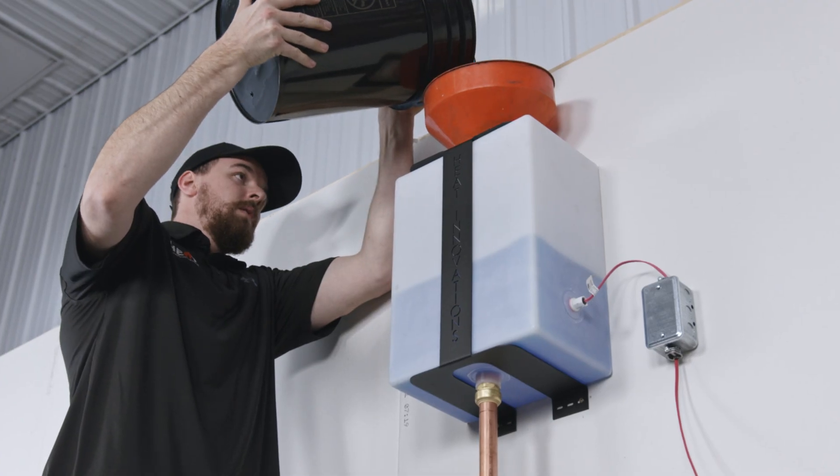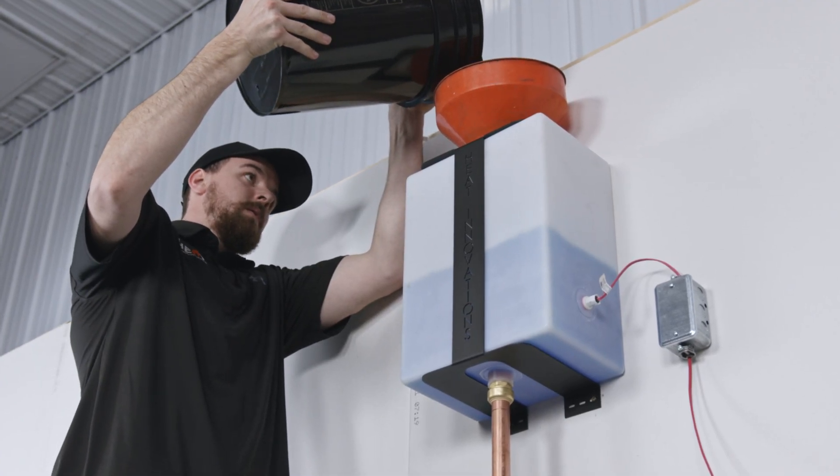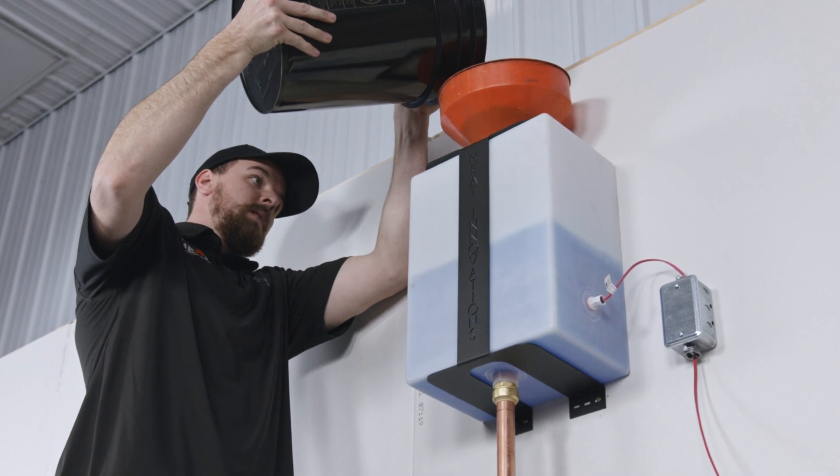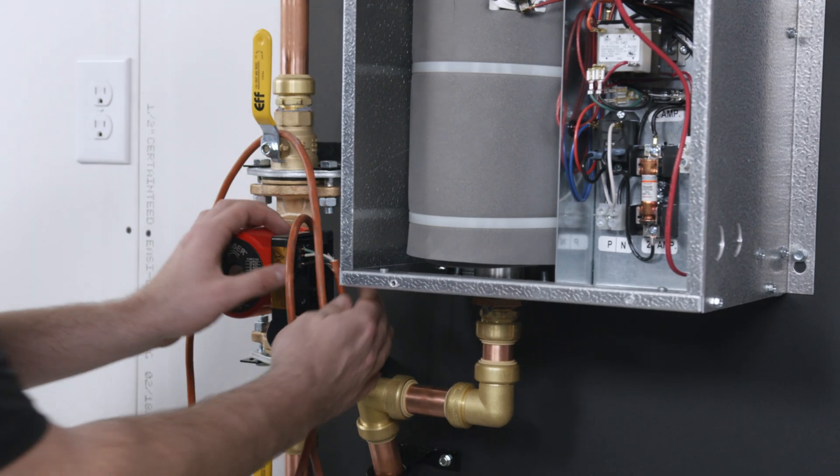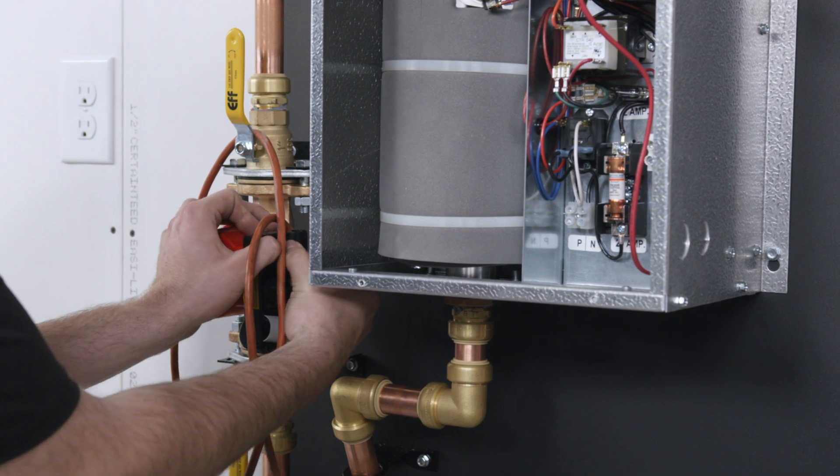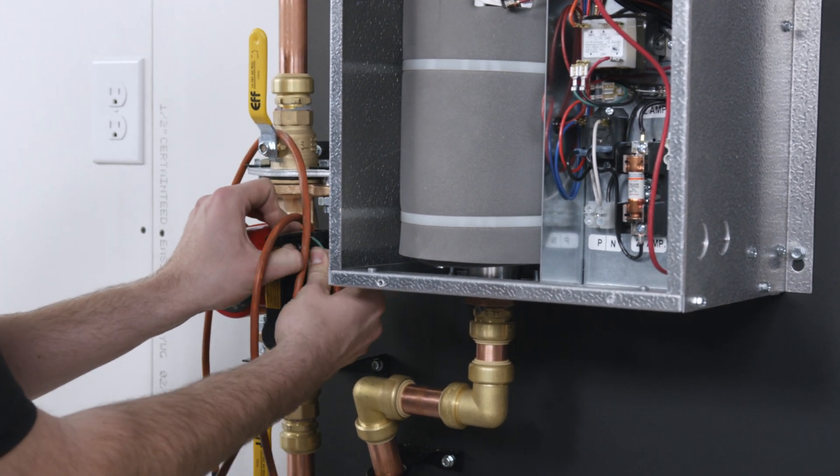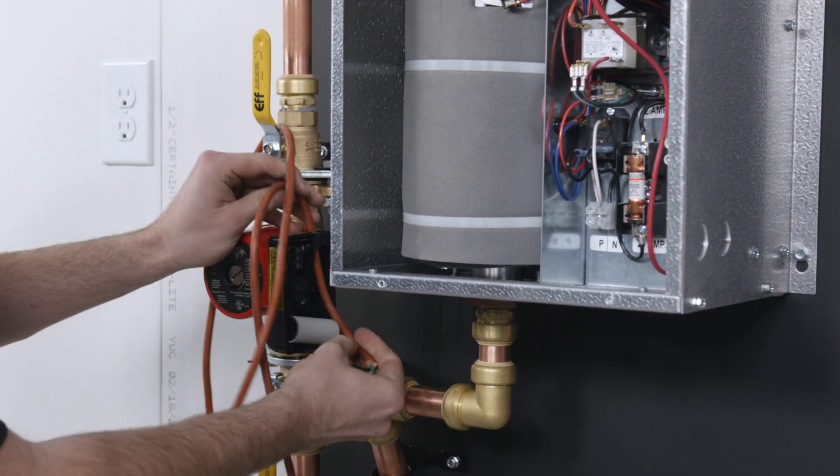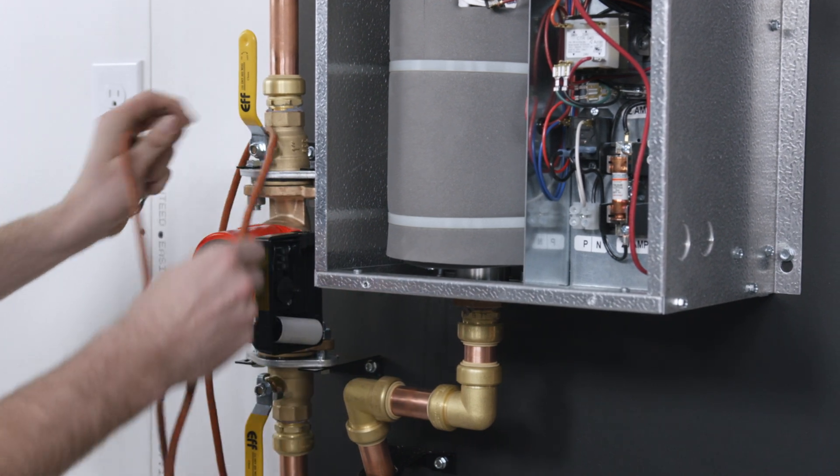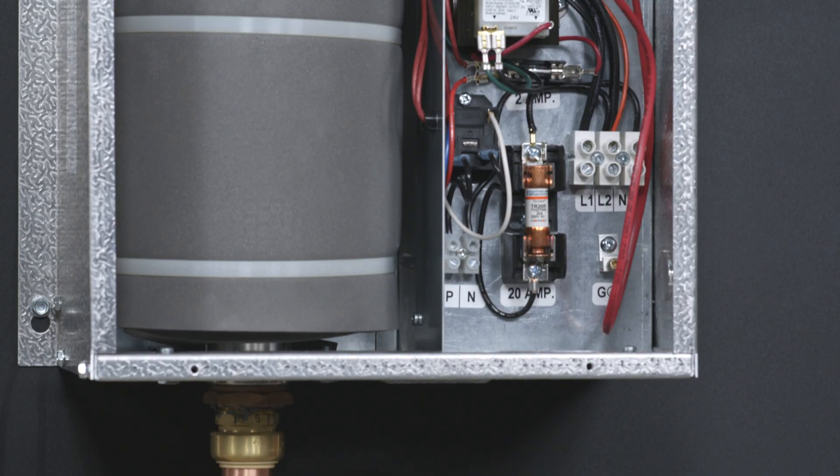After the system is purged of air, you may need to top up the expansion tank with more water and glycol. Call your electrician to disconnect the temporary wire on the pump and connect it inside the boiler to the P and N terminals.